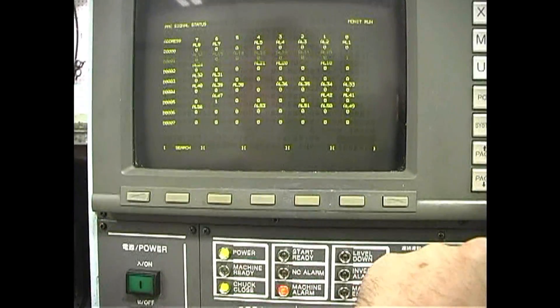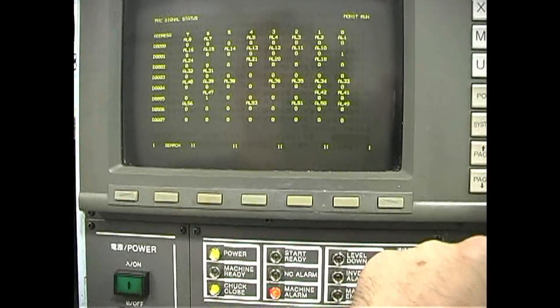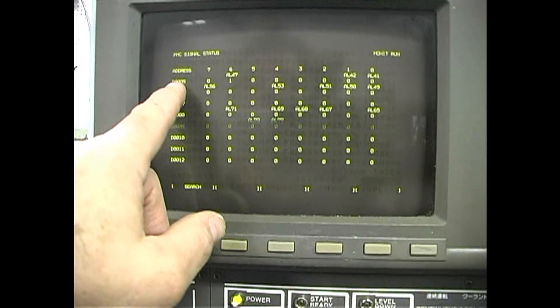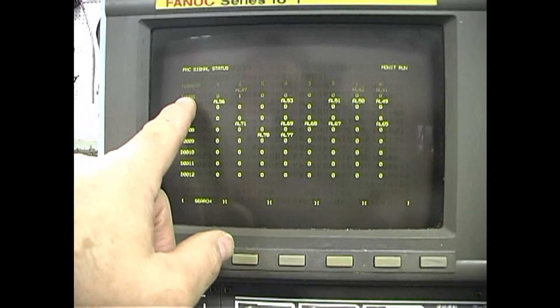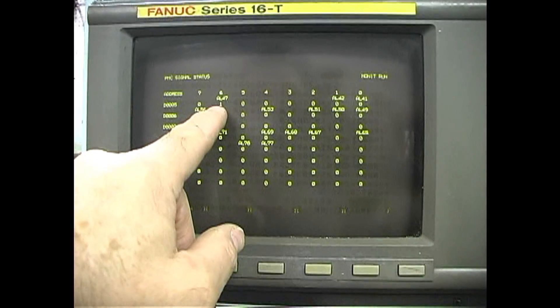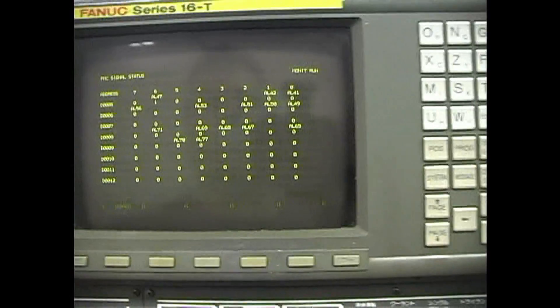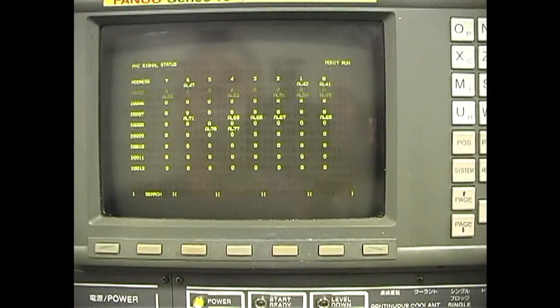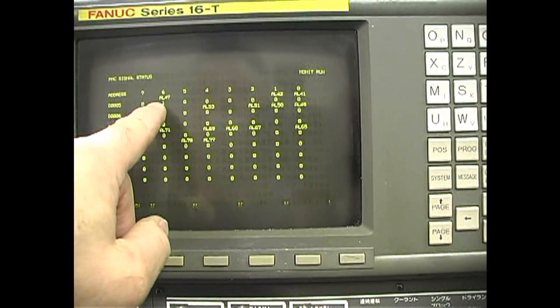These are normally all zeros, and we have to find the one that's a one. We have D5 bit 6 is a one. These are all normally zeros when the machine is in a proper state — so D5 bit 6, AL47.